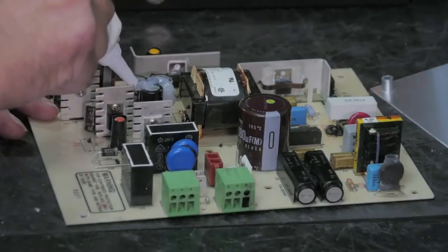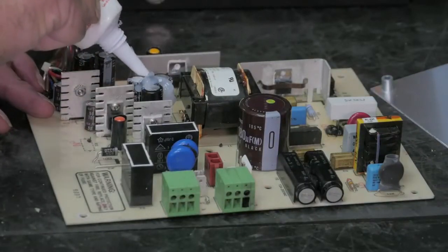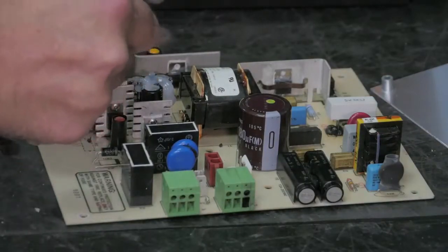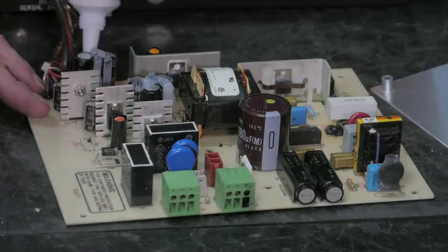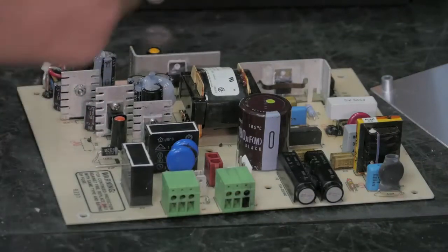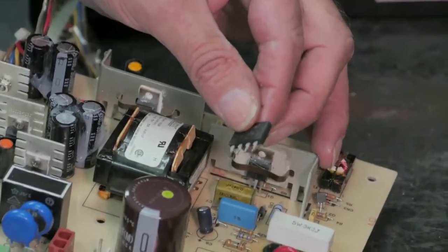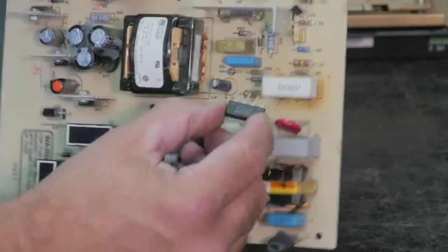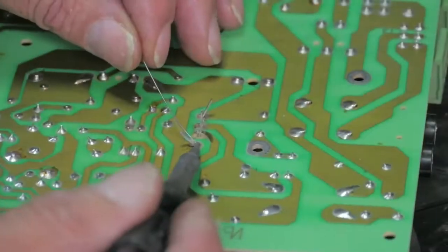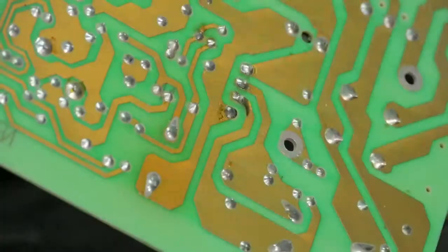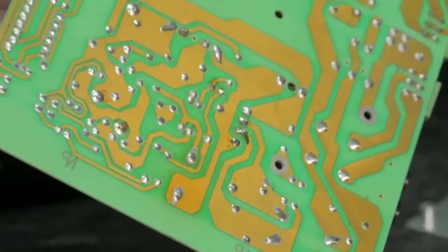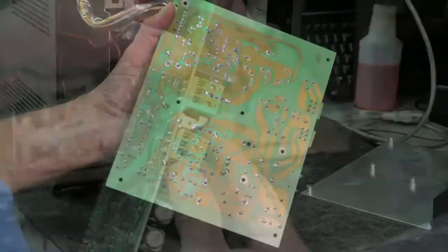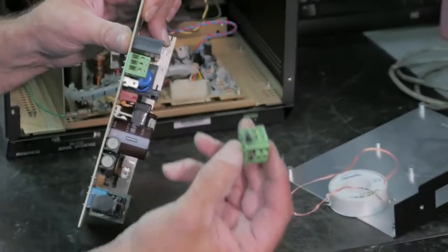Here, the technician has just replaced the line filter caps, as these are high failure components. This will greatly improve the unit's longevity and uptime in service. Next, he is replacing the bridge rectifier. And finally, the bad input connector.